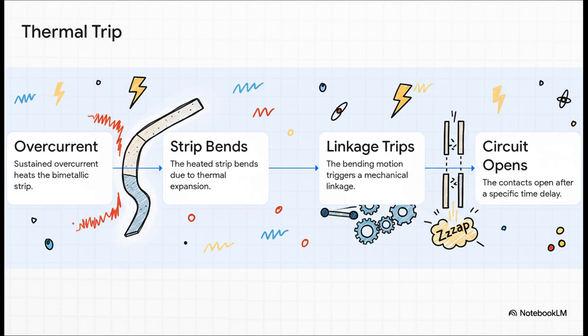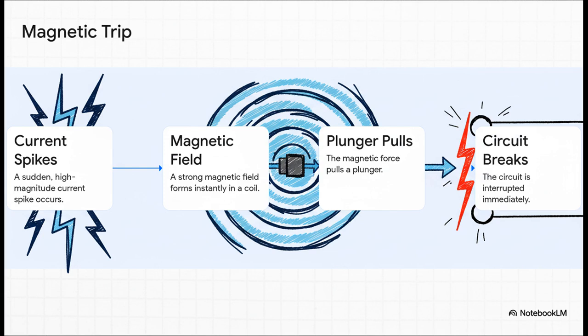Inside, there's this really cool little part called a bimetallic strip. It's just two different metals stuck together. As a long sustained overcurrent heats them up, one metal expands more than the other, and that makes the whole strip bend. Think of it like a slow, deliberate thermostat. Once it bends far enough, click, it physically trips a switch. And it has a built-in time delay, so it won't trip for just a harmless little power spike. Pretty smart.